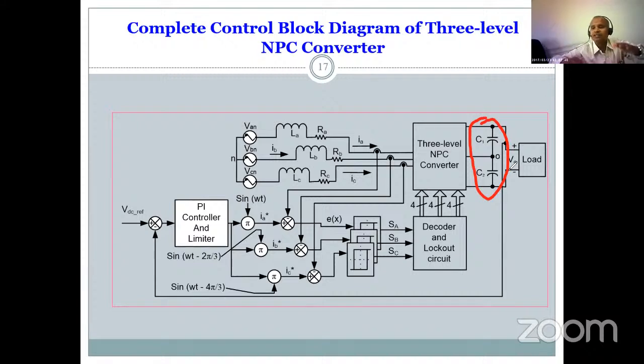As soon as there are two unbalanced sources with a large inertial load, the system will start vibrating. And as soon as mechanical vibration starts, within a few seconds the complete system will collapse, because you are controlling the electrical side while the mechanical vibration is on the other side.